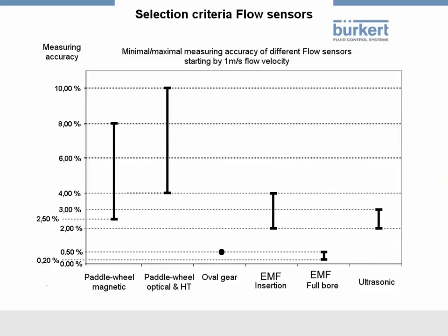Other important criteria are measuring errors and measuring accuracy, which are depicted in the following diagram. This shows clearly that the precision of insertion EMFs is similar to that of ultrasonic sensors, but considerably more precise than that of paddle wheel sensors. The most precise sensors are the full-bore EMFs and the oval gear sensors. Further criteria are the pipe diameters and flow quantities.